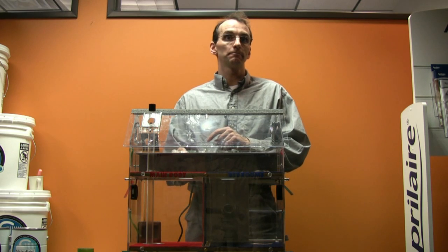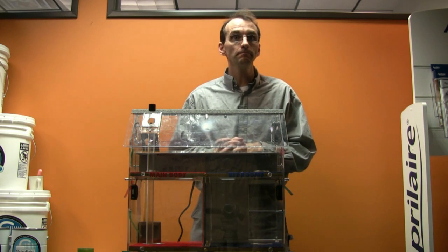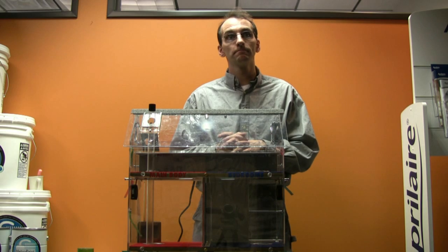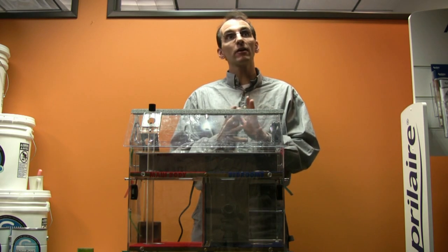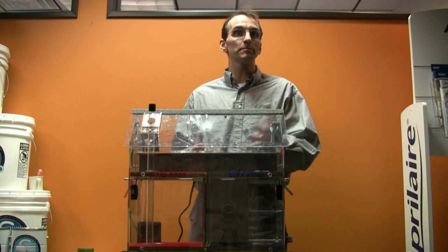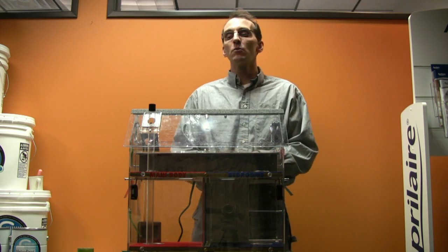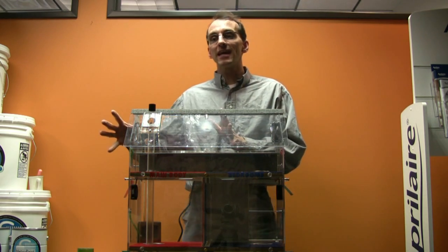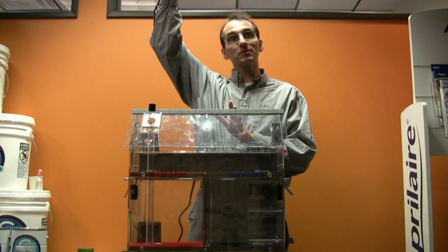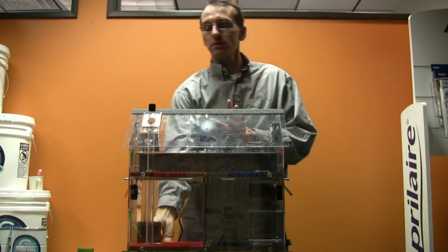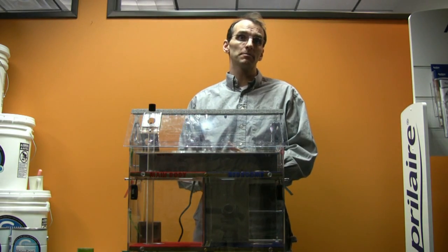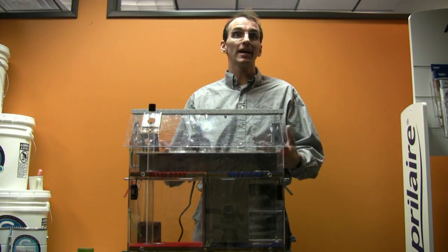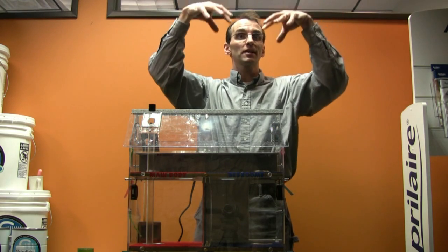So if that's just supplying air to the furnace, why does it matter if it's coming through vents or through leaks? Well, for air quality, you might not want to be sucking the air out of your basement or garage. That's a separate issue. What this is doing is, instead of pulling air from the part of the house where it was supposed to pull the air, it's pulling it out of this basement where we have our water heater. So it depressurized the basement and could end up causing the exhaust to actually come down into the basement instead of getting out of the house.